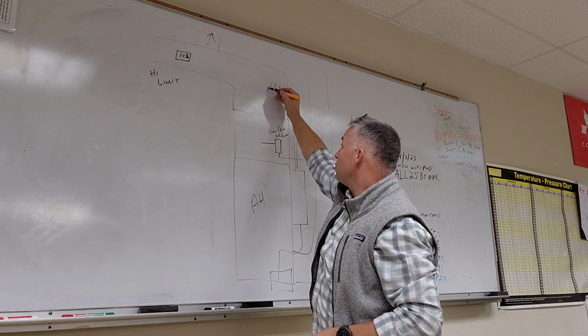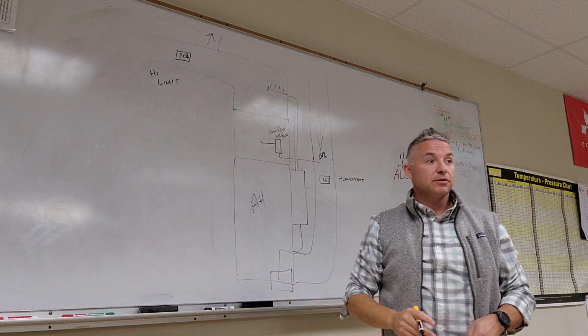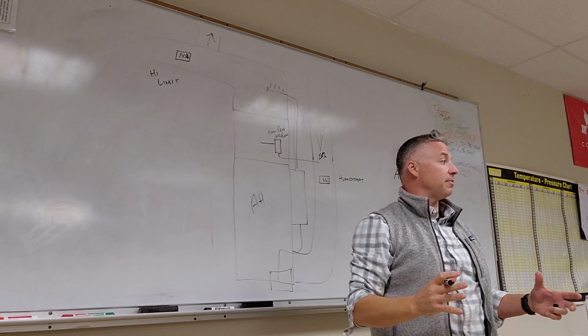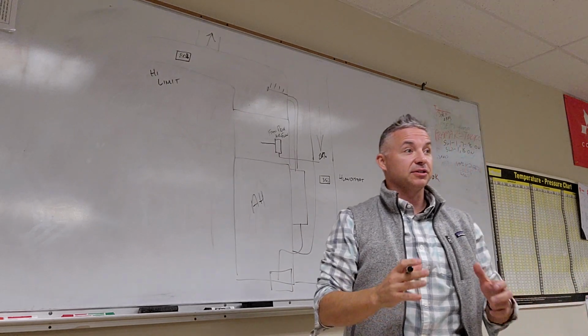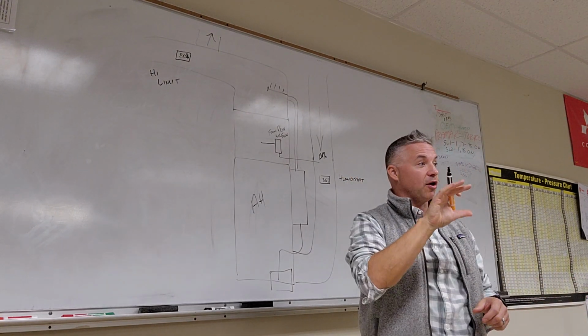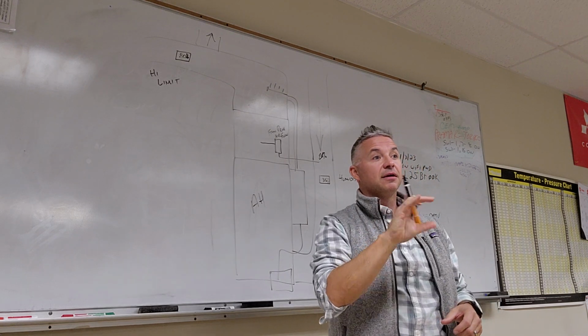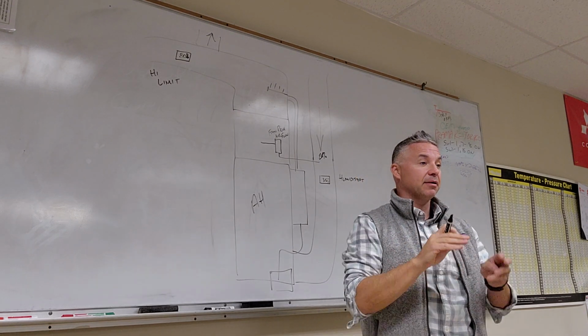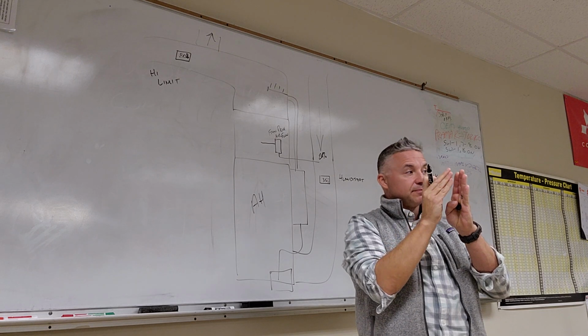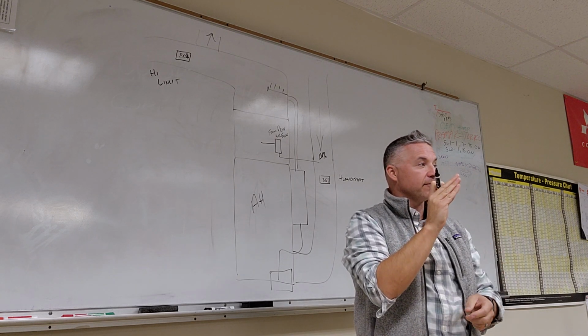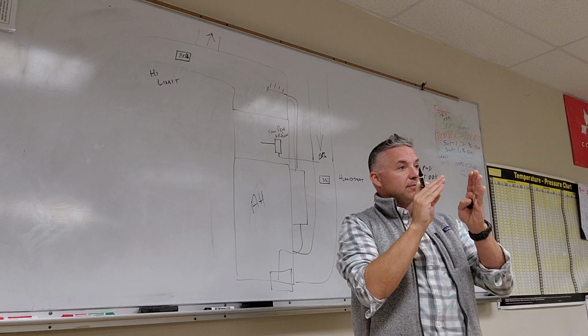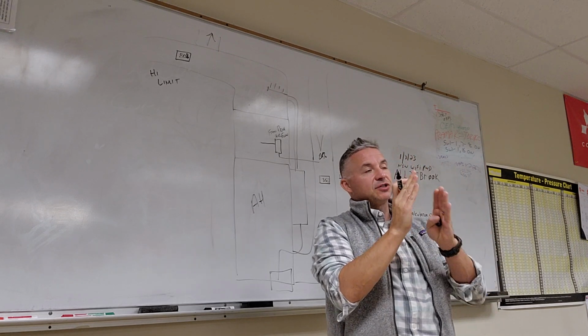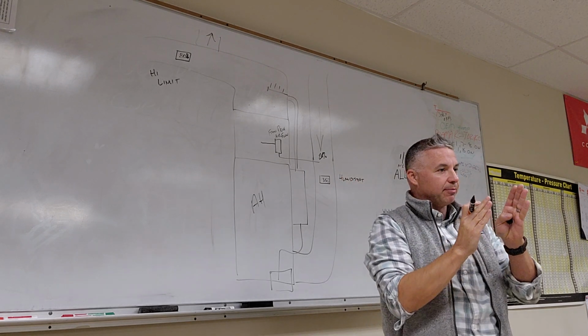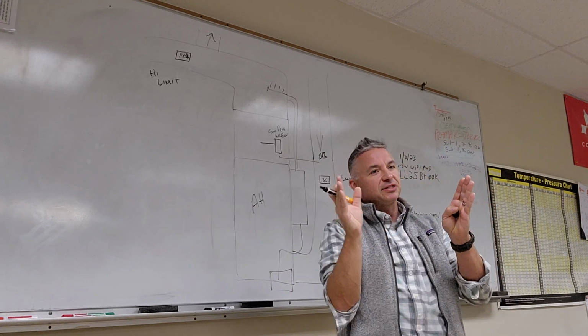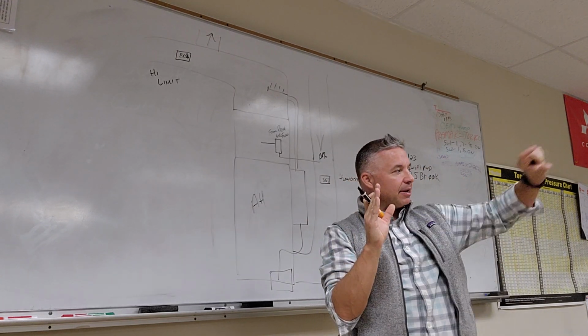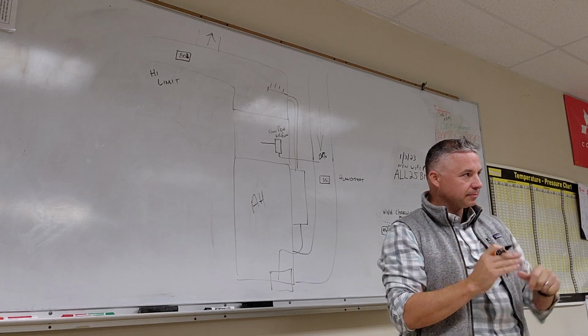those old school nozzles, the first one that I showed you, the reason we don't use those and the reason the manufacturers went away from those type of nozzles is sometimes the ends of those would pop off because of all that expanding and contracting of that hot steam and the cooling down happening in there. It was a two-piece nozzle, so the end would fall off. So the front of that had like a small screen on it. I wish I had one for an example. It had a small screen on it, which would kind of create some back pressure and limit how much steam is coming out of that nozzle.